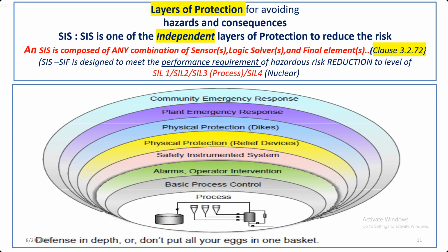So the process should be selected which is inherently safe. That is the first layer. The second layer is BPCS, as we mentioned, the basic process control system. The third layer is alarms and intervention. An alarm does not do any work other than cautioning you by flashing a light or a horn. It doesn't do anything other than that. So that is the third layer, but every layer has to be an independent layer. Independent means BPCS will not depend on the alarm layer. That means you must not derive the alarm from the same transmitter which you are using for process control, but use a separate transmitter and a separate alarm system for alarms. Then it is a safety layer.